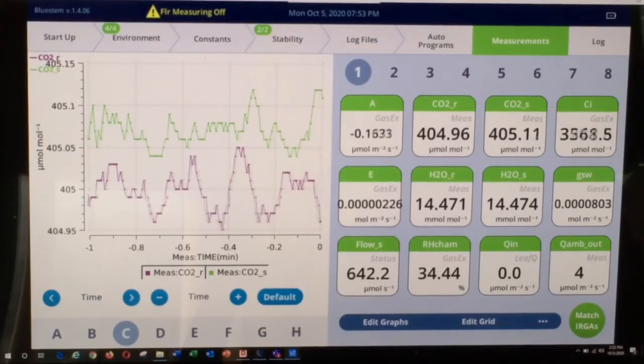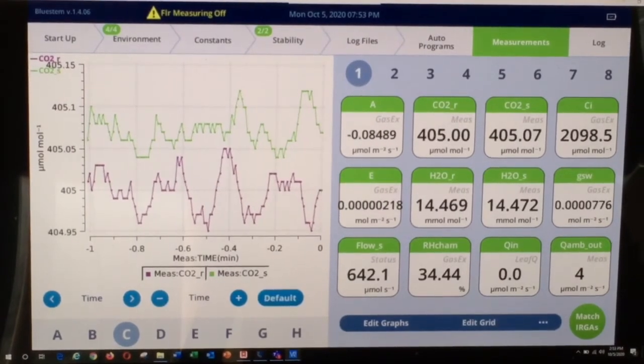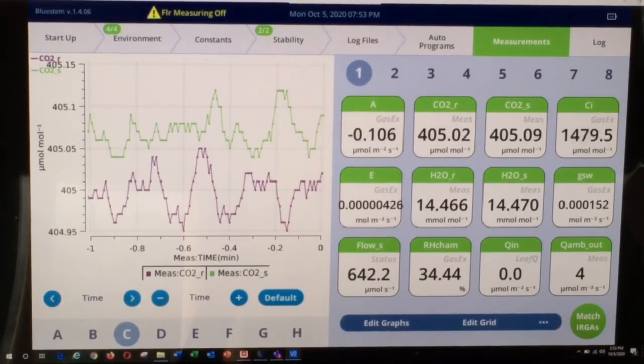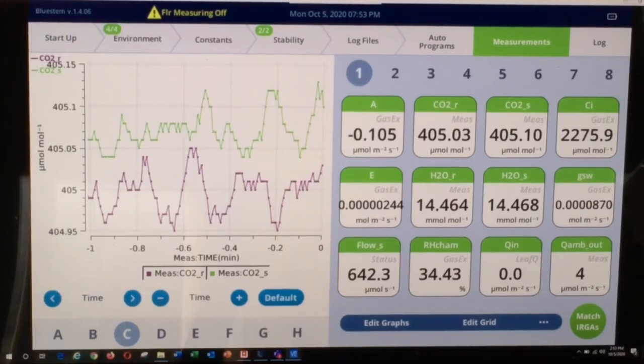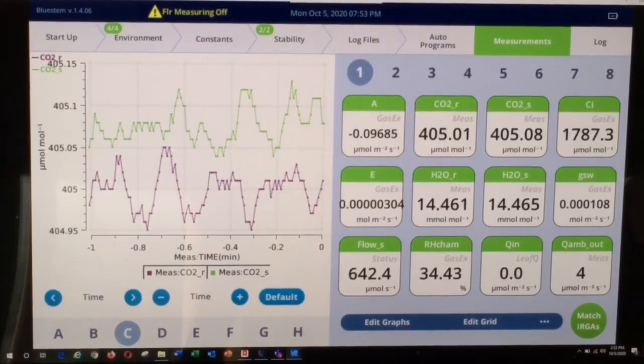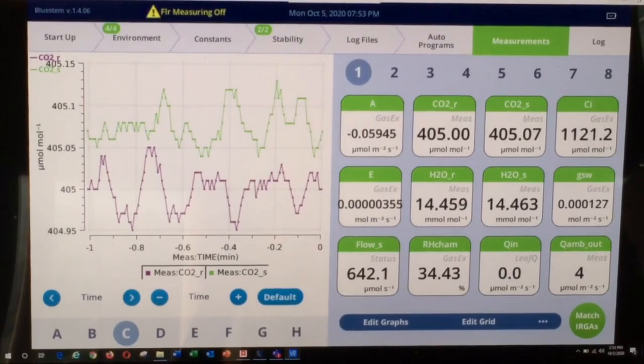Range matching is a new feature that LI-COR has pioneered and introduced into the LI-6800. This feature is very useful for techniques such as the RACiR technique or the new dynamic assimilation technique, where customers want to collect rapid A-Ci response curve data. Please note that range match data should be acquired when the instrument IRGA is well warmed up for best performance. This concludes our overview of range matching in the LI-6800. For further information, you can consult the LI-6800 user's manual or technical support resources at licor.com, or contact your local distributor. Thank you.